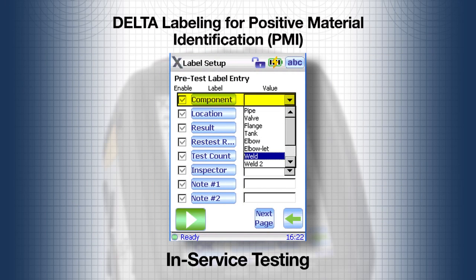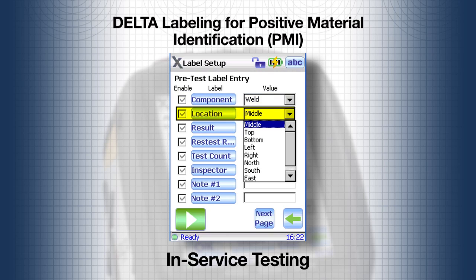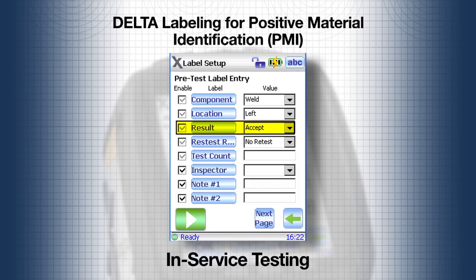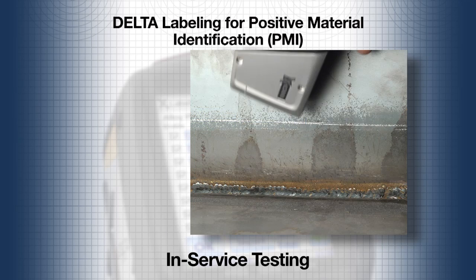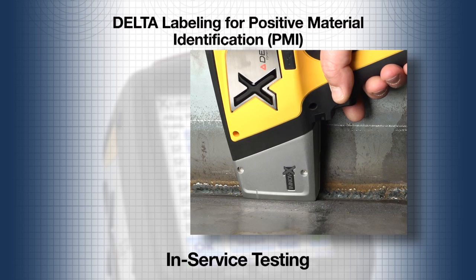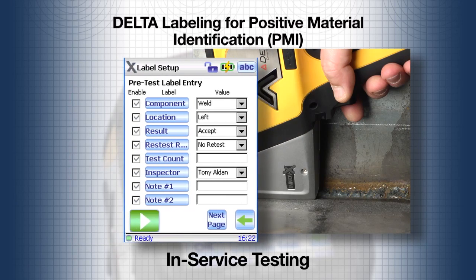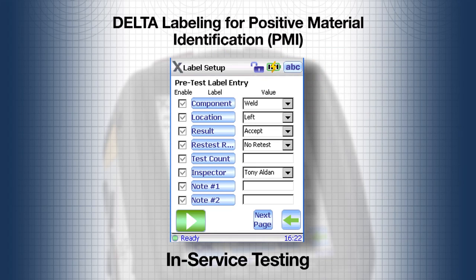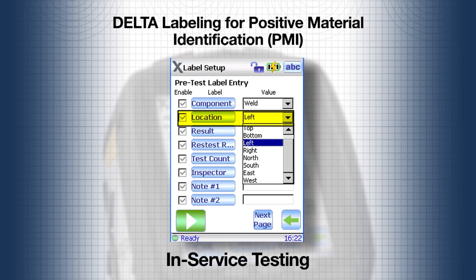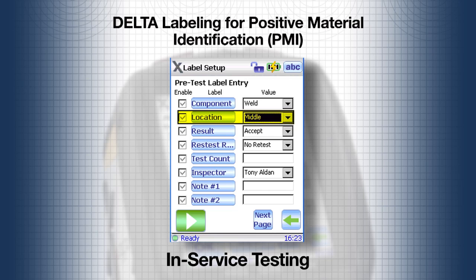Select the component and the location on the component where the first test will be run. The result field defaults to accept, but if the test needs to be rerun, this field can be changed to retest after the test is taken. Place the analyzer on the sample, pull the trigger, and the test begins. For each test, the label window appears before the test starts — it's a simple matter of changing the location of the test and then running the test.